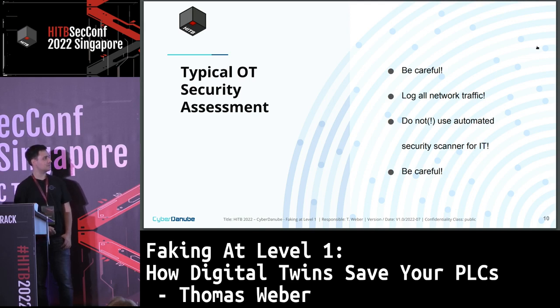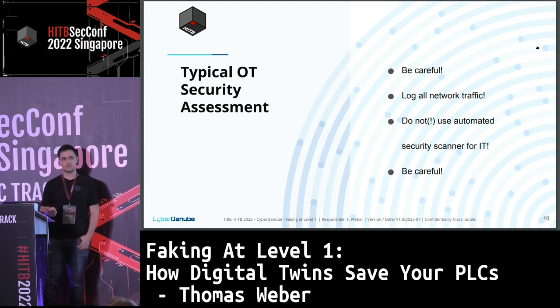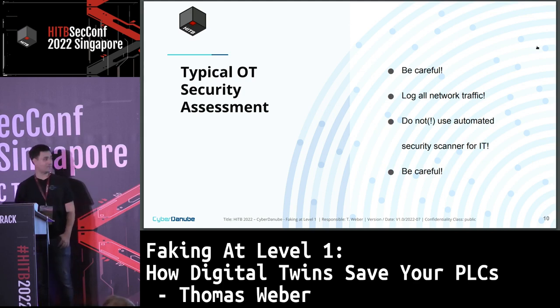And do not use automated security scanners for IT, because those security scanners may just break everything. I had OT security assessments where I just did a port scan, of course during a maintenance window, so it was not the big problem, but about 200 PLCs were just rebooting at that moment. That's bad if it's during the daily work, because then it may break a lot.